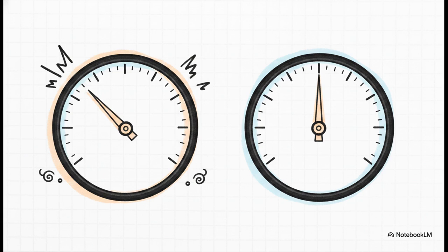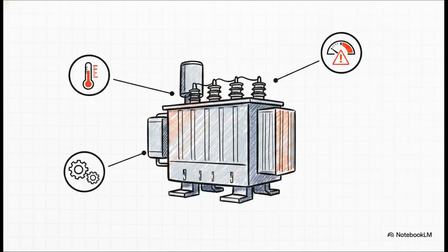I mean, sure, 5 steps theoretically give you a 12.5% range, but in the real world, installations rarely run perfectly pinned at their extreme top or bottom taps. When you're fighting a 7% swing on a 5-step changer, your operational buffer is incredibly marginal. This is exactly when and why you'd specify the 7-step oil-immersed configuration instead, giving yourself some actual breathing room. Okay, so look at that. You've essentially mastered the fundamentals here.